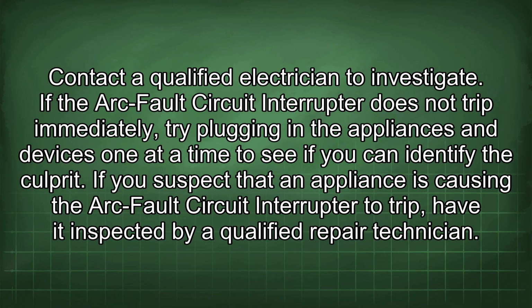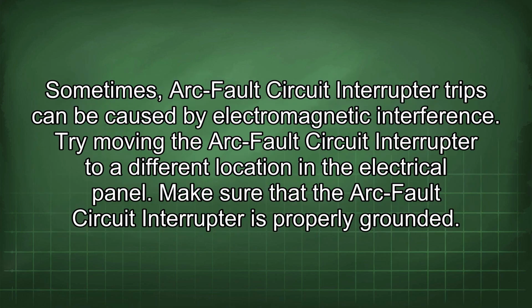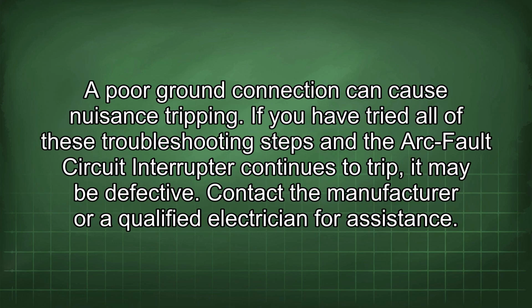If the arc fault circuit interrupter does not trip immediately, try plugging in the appliances and devices one at a time to see if you can identify the culprit. If you suspect that an appliance is causing the arc fault circuit interrupter to trip, have it inspected by a qualified repair technician. Sometimes arc fault circuit interrupter trips can be caused by electromagnetic interference. Try moving the arc fault circuit interrupter to a different location in the electrical panel. Make sure that the arc fault circuit interrupter is properly grounded. A poor ground connection can cause nuisance tripping. If you have tried all of these troubleshooting steps and the arc fault circuit interrupter continues to trip, it may be defective. Contact the manufacturer or a qualified electrician for assistance.